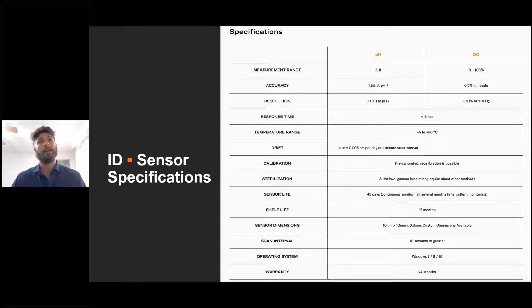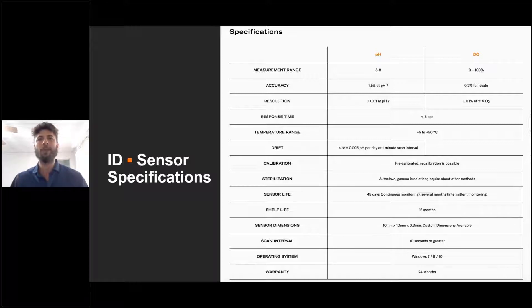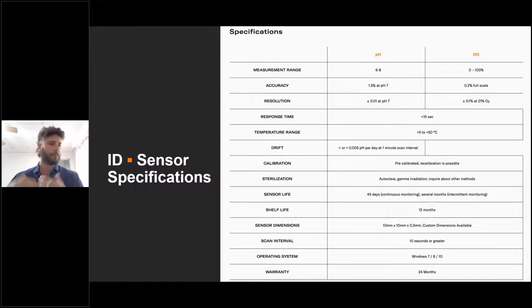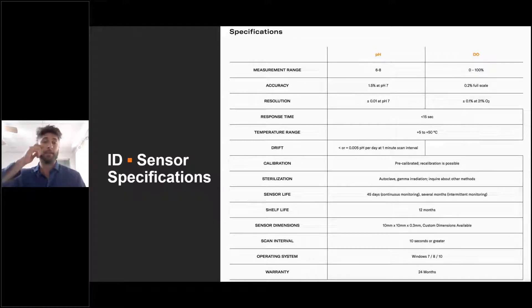Optical sensors are a newer technology breaking onto the commercial scene. What makes them great is how minimally invasive, versatile, and small they can be. These sensors can be steam sterilized or gamma irradiated. Most importantly, they can be very tiny — the standard size is one centimeter square and 0.3 millimeters tall, just a couple pieces of paper stacked in terms of height. They can also be as small as three millimeters in diameter. If you have three millimeters of space in your bioreactor, T-flask, or any vessel, you can use these sensors. They are also single-use and inexpensive — a plug-and-play method with no sterilization needed afterwards, reducing contamination risk.